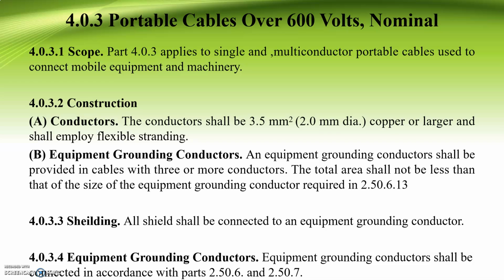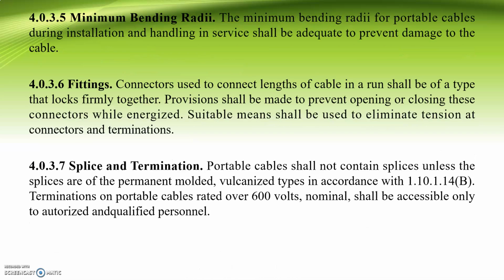So chapter 4.0.3.3, so all shields shall be connected to an equipment grounding conductor. So chapter 4.0.3.4, so equipment grounding conductors. So equipment grounding conductors shall be connected in accordance with part 2.50.6 and part 2.50.7. So chapter 4.0.3.5, so minimum bending radii. The minimum bending radii for portable cables during installation and handling in service shall be adequate to prevent damage to the cable. So chapter 4.0.3.6, connectors.